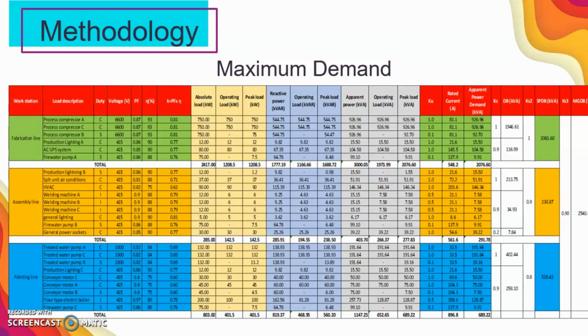Then to calculate the maximum demand, the suitable utilization factor, which is KU, and also the diversity factors KS1, KS2 and also KS3 for each load are identified by considering the duration of the operating loads in the factory. For example, the heavy machines like welding machine A, welding machine B and also welding machine C, and also the heavy conveyor motor C, conveyor motor A, and also conveyor motor B. We decided the suitable diversity factor is 0.9. So then by multiplying the KS3 with the sub-plant distribution board SPDB, our total kVA for the sub main generation distribution board SMGDB is 2540.61 kVA.